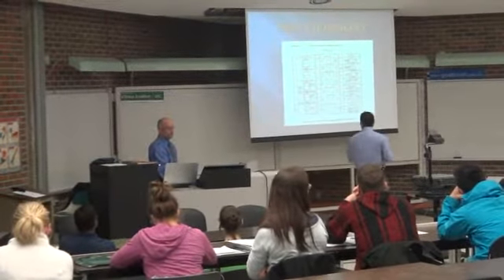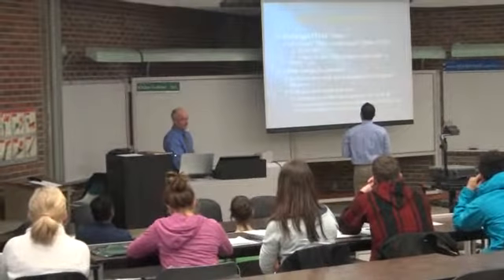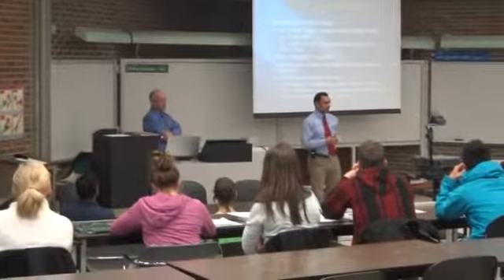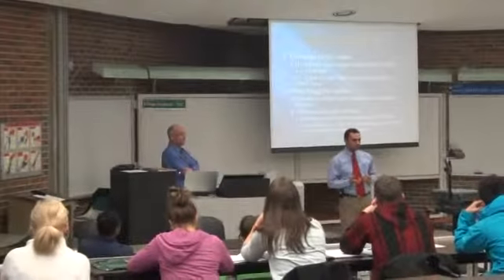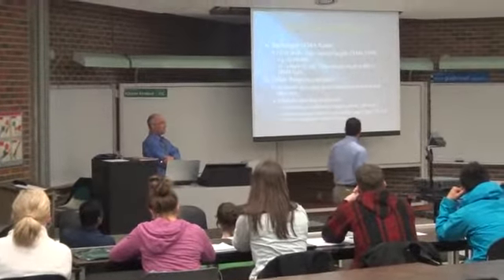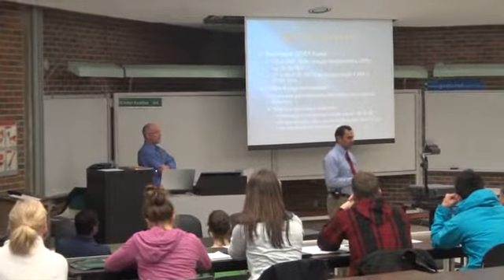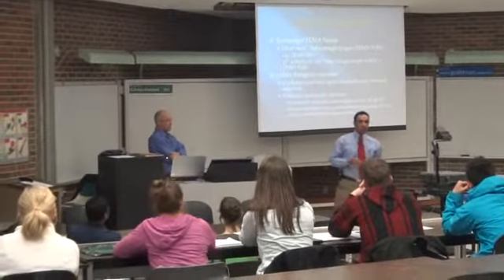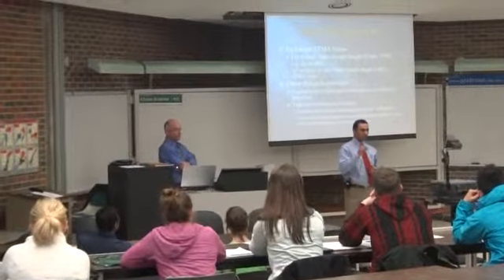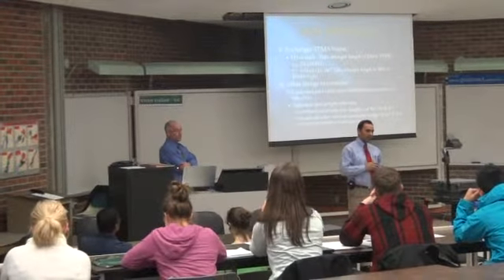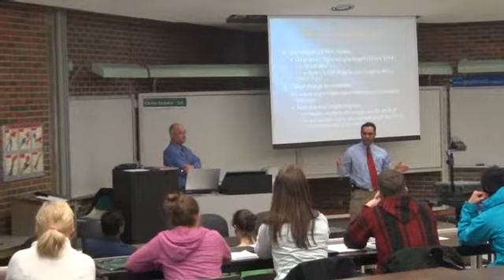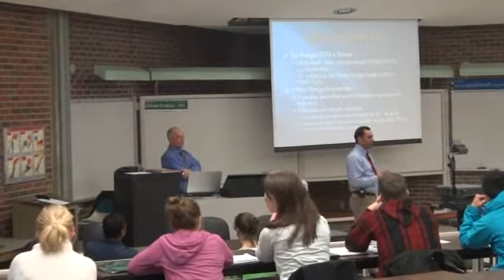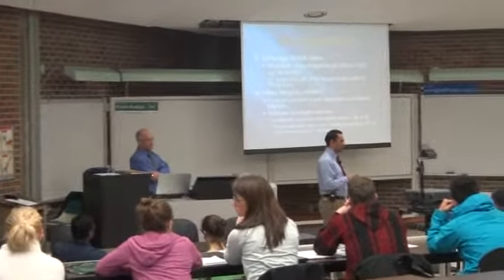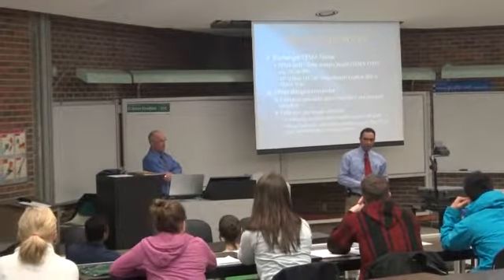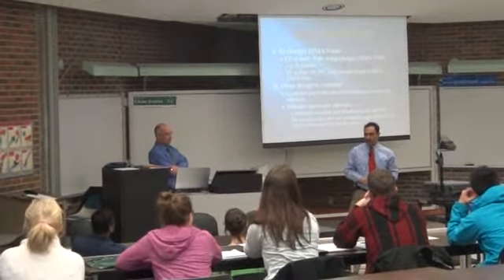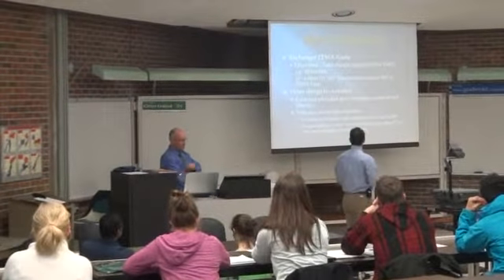Same thing on the rear heads. So how do you name an exchanger? Normally, when we talk in industry, somebody will tell us 23-240 BEU. What does that mean? So 23 is the 23-inch shell ID, and 240 is the tube length, and BEU is the TEMA type you selected. B is your front head, E is your shell, and U is your rear head. So that's the way you form a TEMA type.